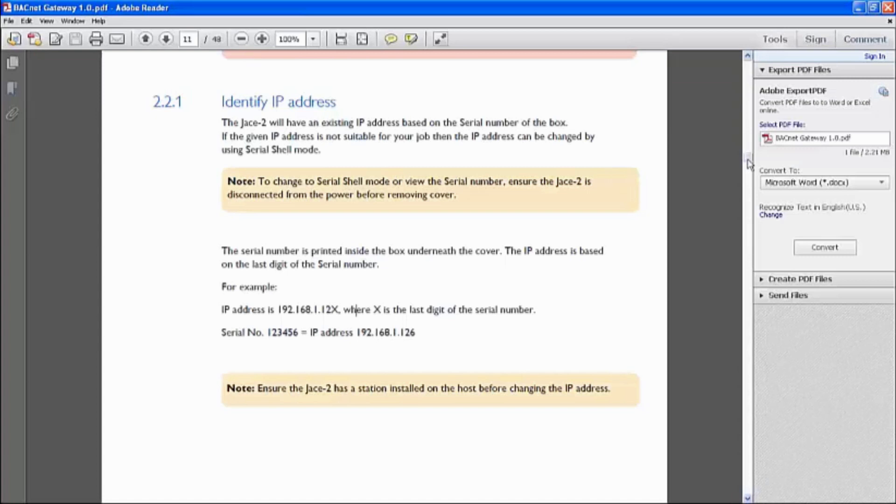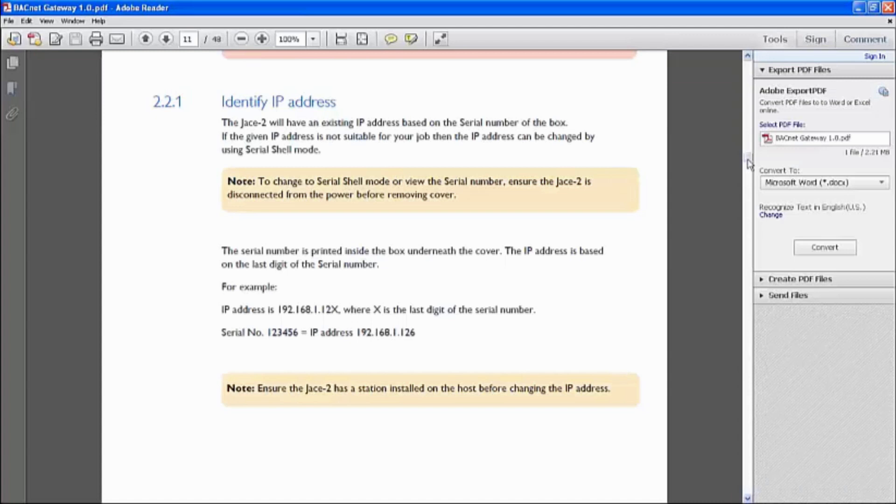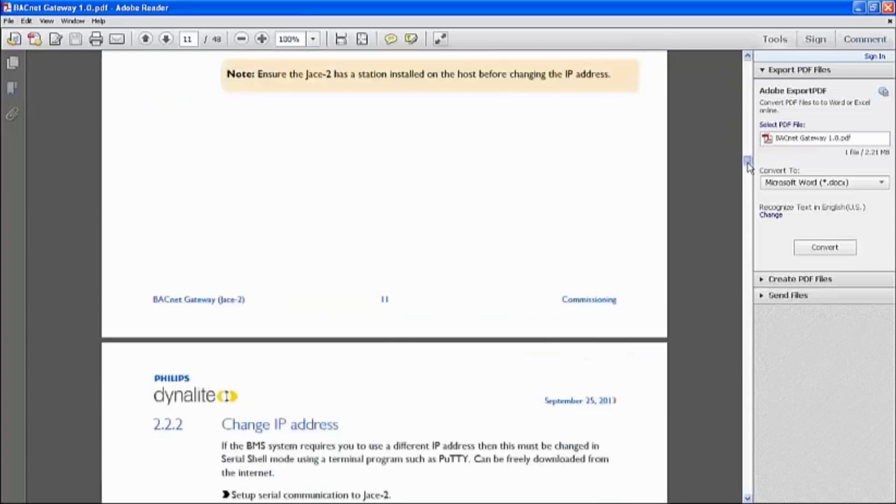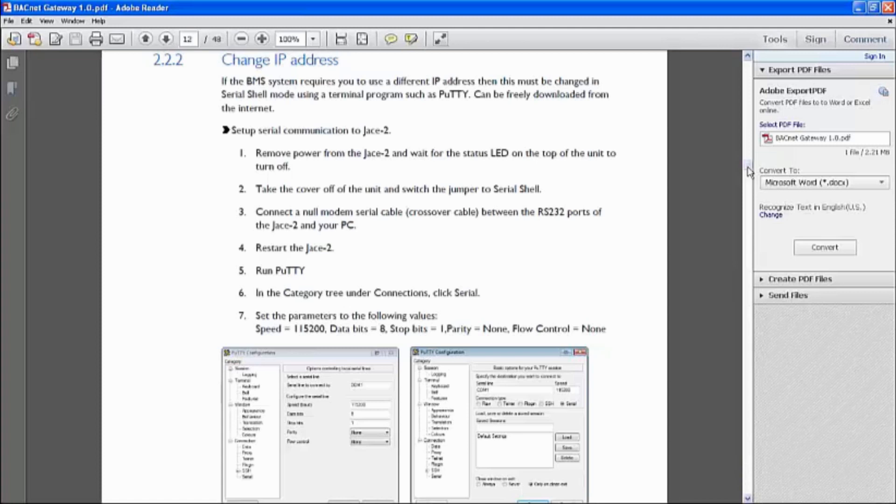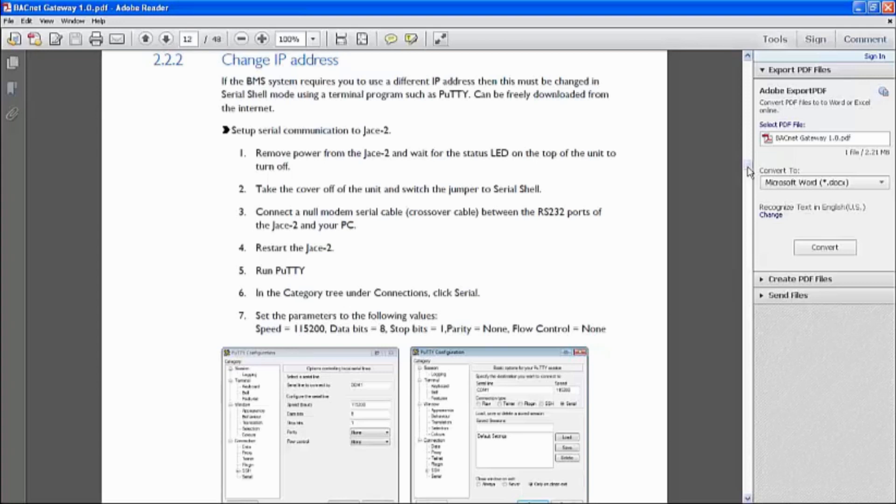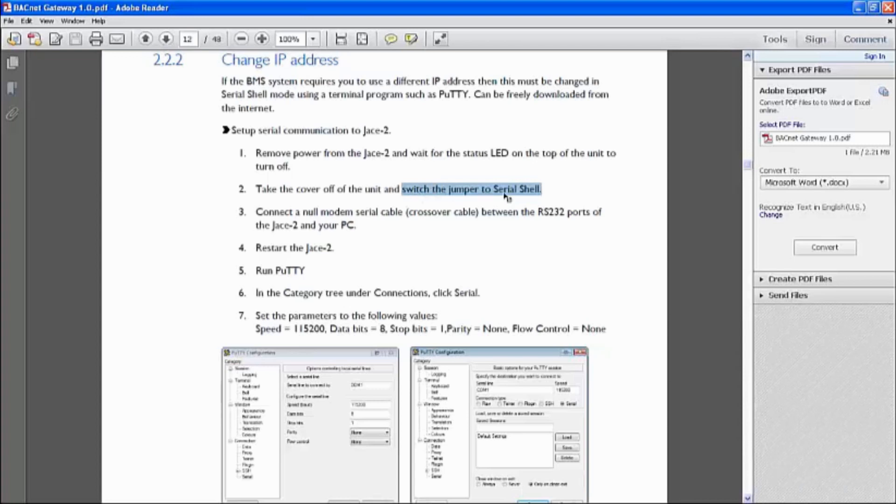It could be original, as we say, it could be 192.168.1.123, but IT might give you a set of IP address that says, no, you know, do this octet range between 10.0.0.0 to 255. So we can actually change the IP address easily. But changing of IP address cannot be done through remote access through the web browser of the JACE unit, but actually through a third-party software program called Putty. This can be downloaded free online. And just by following this step-by-step procedure, you're able to change this IP address fairly easily, probably in a minute or so.